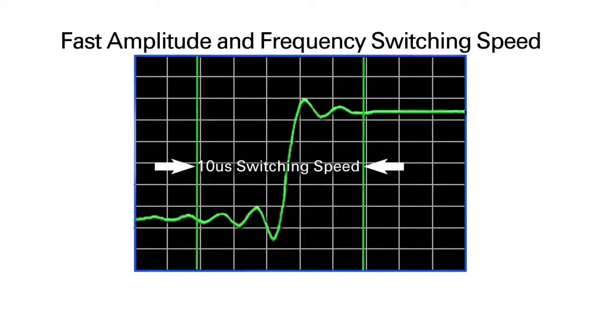In addition, we have a new baseband tuning algorithm that allows us to switch both amplitude and frequency in an unprecedented 10 microseconds.